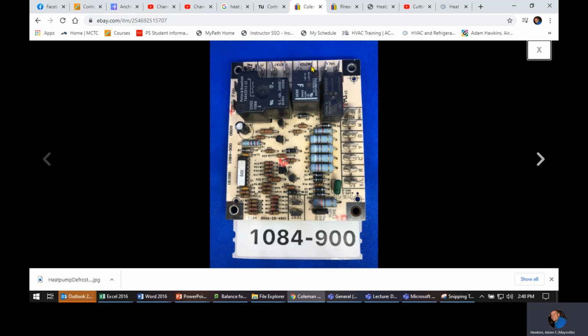If it's just a switch that is made or broke, and you test that switch and it's open, and you know that you have pressure. So let's say it's a low pressure cutout, and you check it and you know you have pressure, your gauges are fine. You can jumper that out, and that would get you by until you can get something done. In that case, you wouldn't be replacing the board, you'd be replacing the switch.